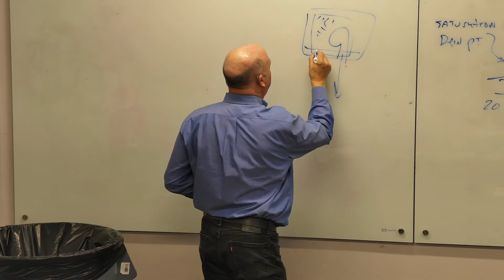And you've got a water line coming over here and you've got a toilet float there with a valve to keep the water level where you want it. And this is 100% outside air. This fan is blowing down and it's sucking air in through 3 sides where you've got your pads. The way that works is it starts off at our, we said 75, 50%, and this was 61 and a half, right? The water follows the air temperature follows the wet bulb line. And so it creeps up this direction. It's trying to get to saturation, right? Because we've got it going through this wall of fiberglass that's all wet. And so it becomes more and more saturated.